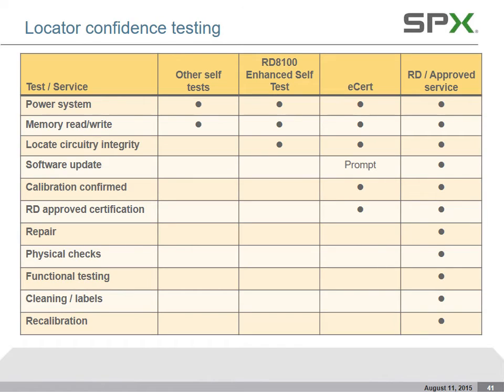So you have the self-test that the unit can do manually, that every locator can do out in the field, and then you have the enhanced self-test, which is on the 8100 series. The self-test on the 8100 series looks at the locator integrity, whereas the other self-tests and the prior versions like the RD400 and the 4000 were mainly just checking to make sure the screen was working. And then you can take it a step further on these 8100.